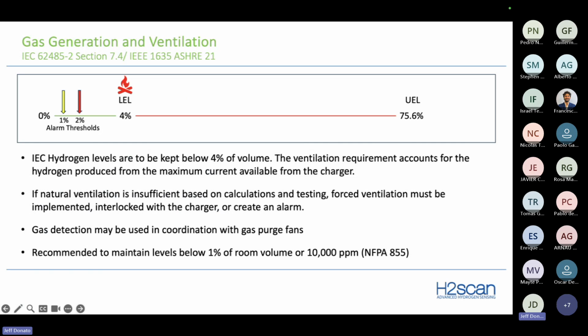So when we talk about hydrogen and where we see the alarm threshold set, and also what the overall properties of hydrogen are, hydrogen is explosive at 4%, and that is what we call the lower explosive limit. The upper explosive limit, which is basically where it stops being explosive, is 75.6%.